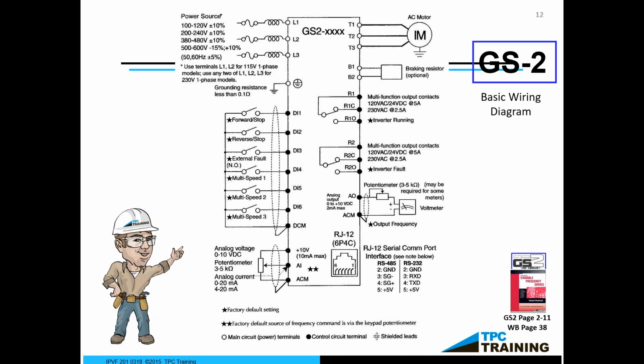Maybe it's just an indicator light. You want to know when it's running. You want to know when it's not running. You'll be able to do that also. And you'll see on that AO, the analog output. Maybe you have a SCADA system, a supervisory control or data acquisition system. You need to know some sort of linear or proportional output based on the speed. A 0 to 10 volt output. Some of them have a 4 to 20 output. A lot of them have a 0 to 10. You'll be able to provide that to your system.